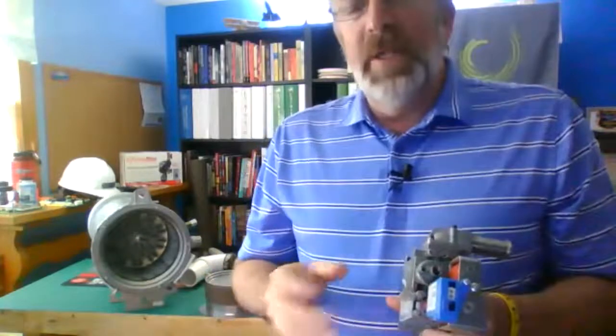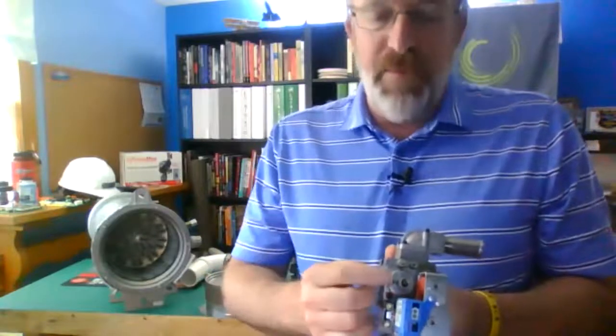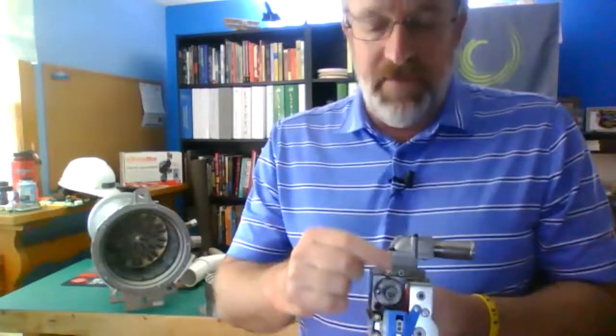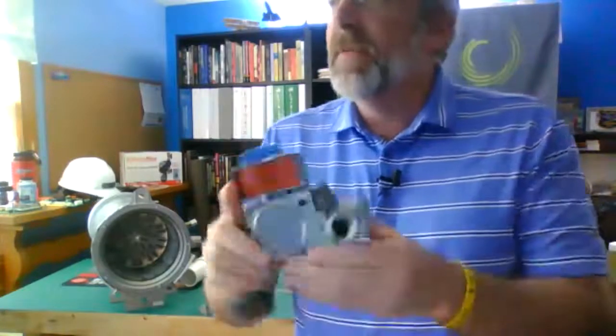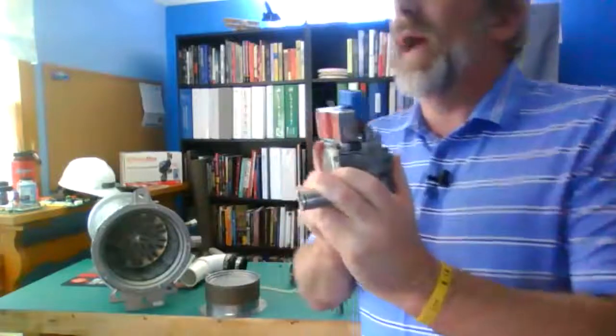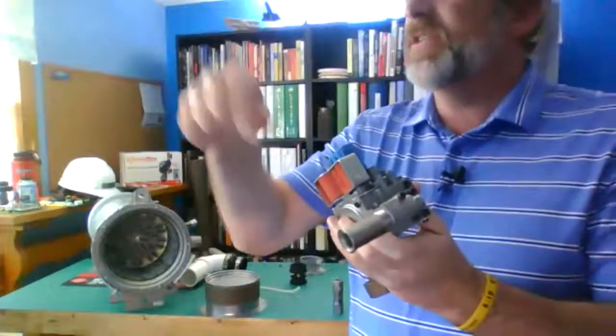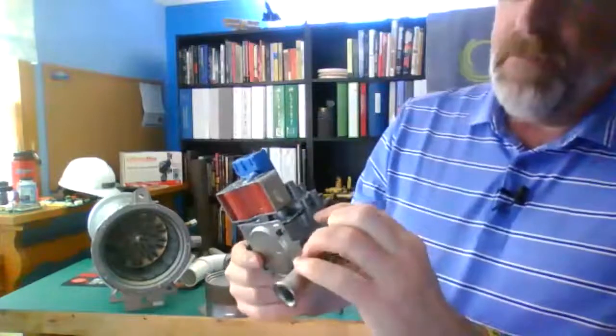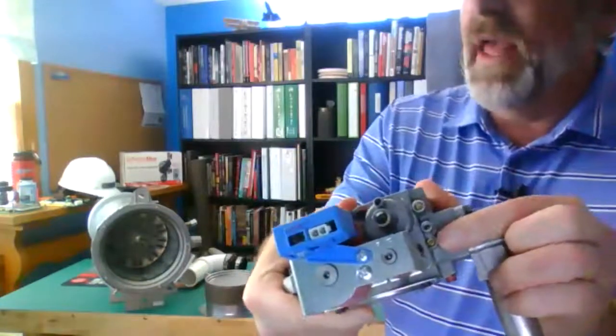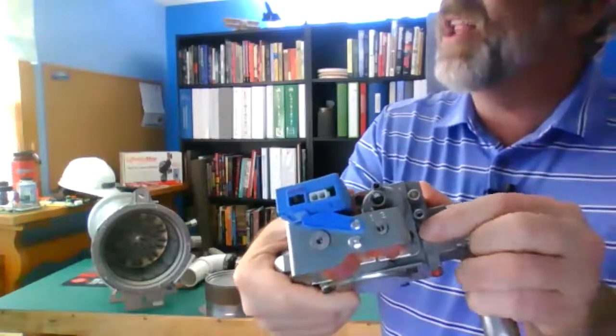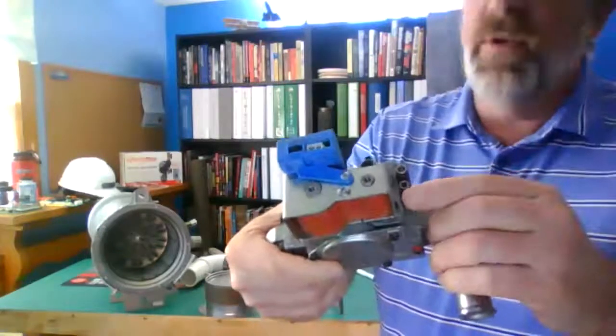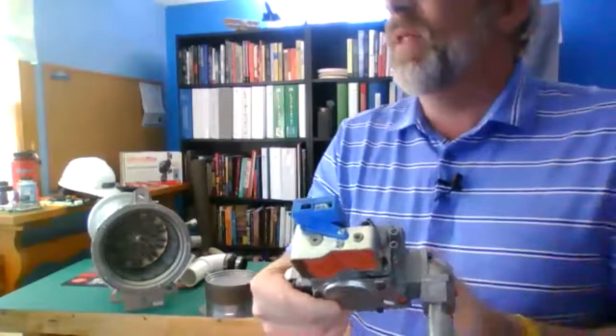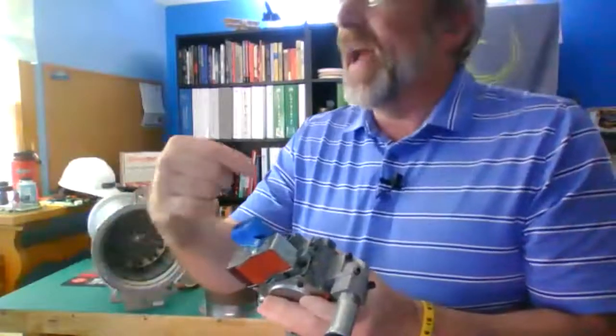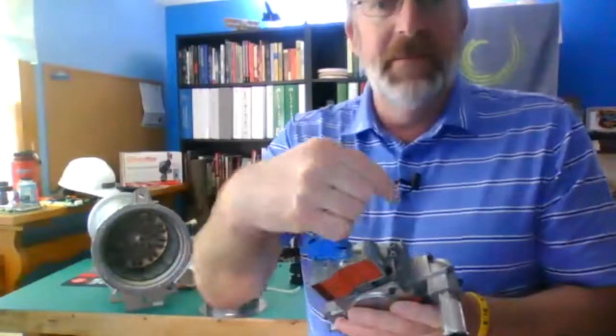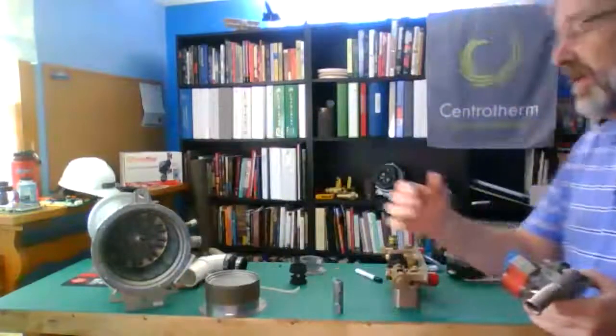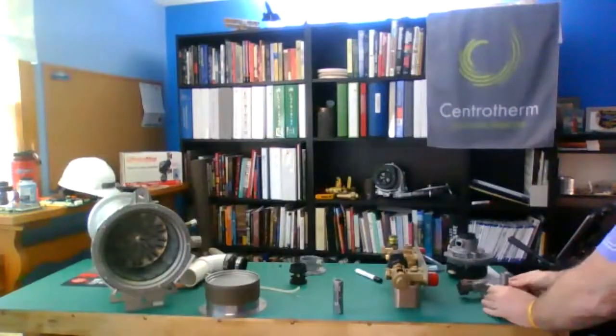And it's not so much a specific low fire or high fire, but it's most responsive on your analyzer at these spots here. Now, if you're dealing with one of these that's way, way out of whack, somebody's been there just adjusting, something like that. This guy here, that screw generally wants to be pretty close to flush. If it's sticking way out, or if it's way in and you can't get that boiler running, that's a spot to start. Let me see what this guy did before me, and let me get it adjusted back, and start there. All right.